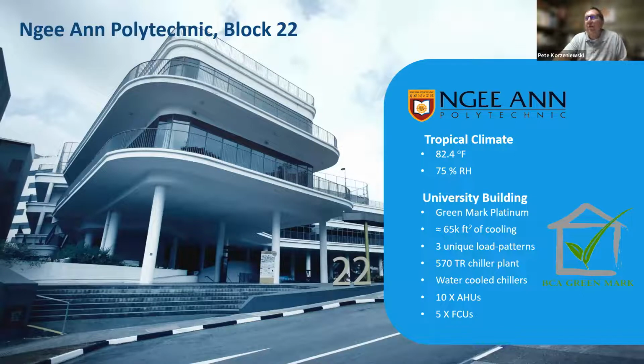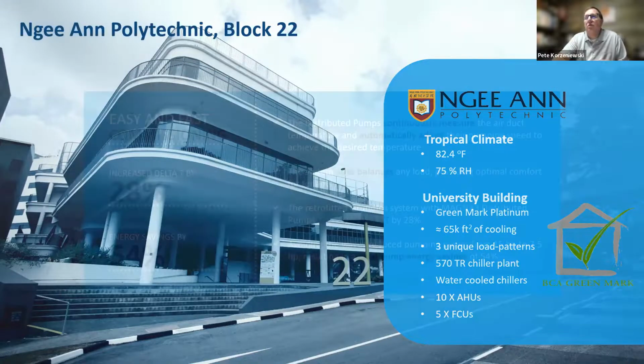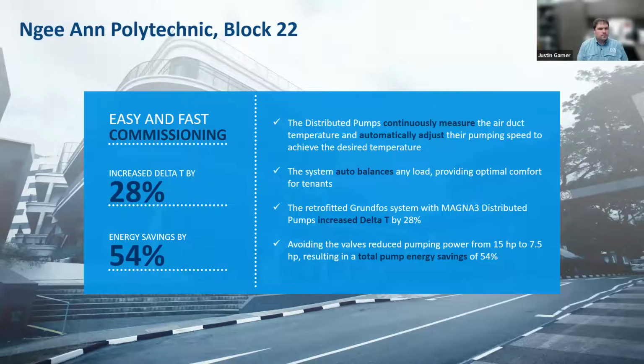So they were looking for other options and started working with Grundfos with an idea around replacing control valves with distributed pumps. Right away, when they made this change and turned everything on, they saw an increase in their delta T of about 30%, and they were using about 54% less pump energy than they were when they were using a larger primary pump set and control valves. So we were very pleased with the results, and we'll talk about that in a little more detail.